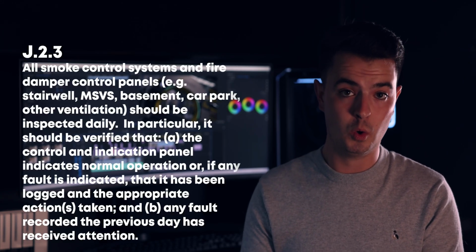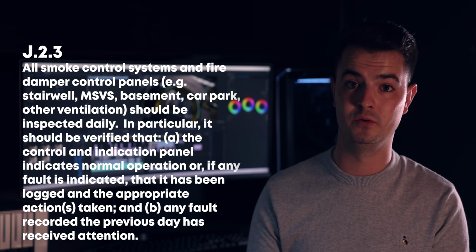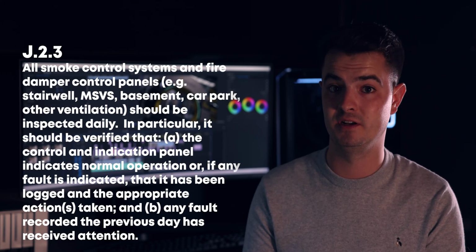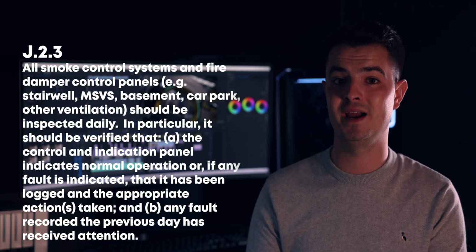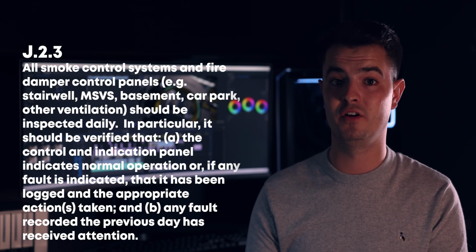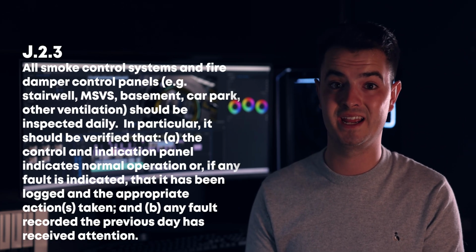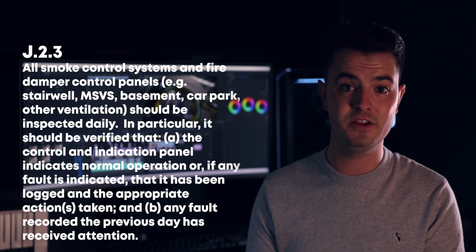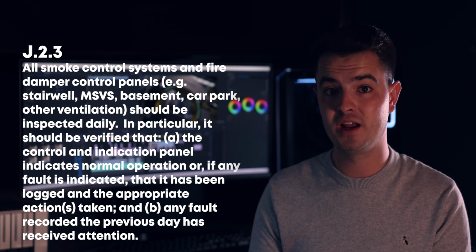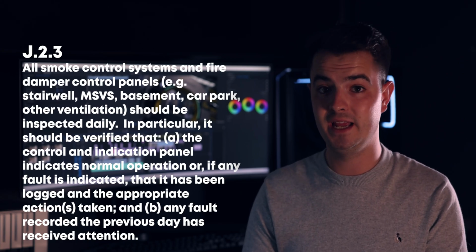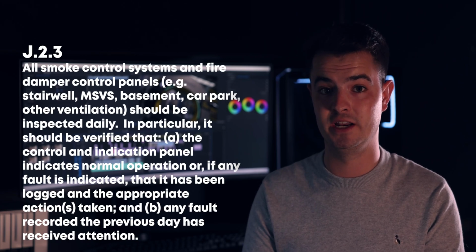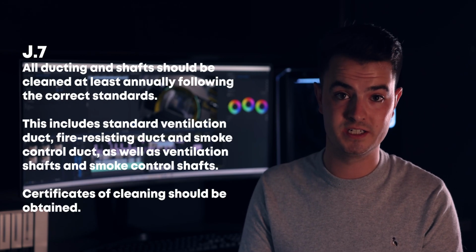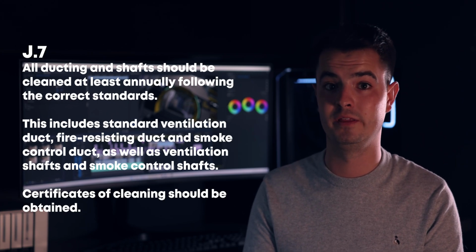I'll run through a series of points which, as far as I can see from looking at other standards and documentation, haven't been raised before. J.2.3, all smoke control systems and fire damper control panels, e.g. stairwell, MSVS, basement, car park, other ventilation, should be inspected daily. In particular, it should be verified that A, the control and indication panel indicates normal operation, or if any fault is indicated, that it has been logged and appropriate actions taken, and B, any fault recorded the previous day has received attention. J.7, all ducting and shafts should be cleaned at least annually following the correct standards.